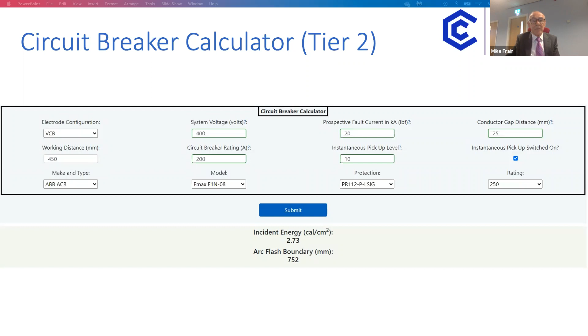And basically what we've done is to create the conditions where if a circuit breaker disconnects instantaneously based on its instantaneous pickup level, then it would produce an incident energy level based on the prospective short circuit current and the arcing current at that point. If it fails to clear the incident energy level, it defaults back to a 2-second disconnection time. So at least we've got a factor of safety there. But we've based it on something like 8,000 common miniature circuit breakers, air circuit breakers, and also molded case circuit breakers as well.